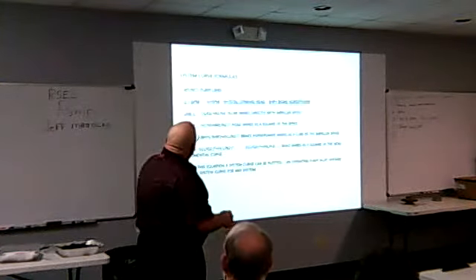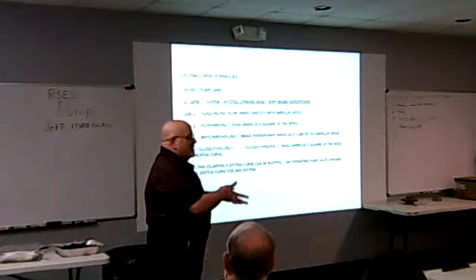Here's the laws that I was talking about. These are the affinity laws. These all apply to a fan. They're the same laws. The flow varies directly with the impeller speed. So like I said, 1160 RPM, 1750, they're going to go up proportionally.